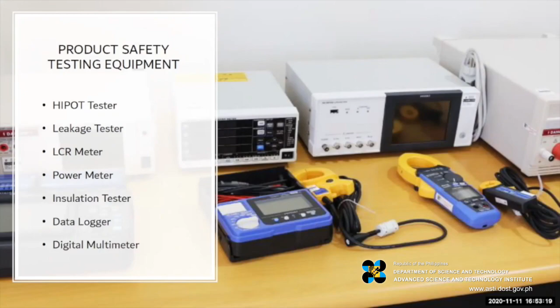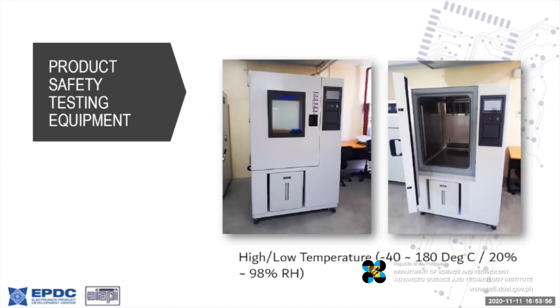All of these, including mechanical tests for impact, burning temperature, jointed finger probes for holes, etc. These are our temperature ovens, from a 50 to 300 degrees centigrade oven, to another with high-low temperature of -40 to 180 degrees centigrade, with humidity from 20% to 98% relative humidity settings.